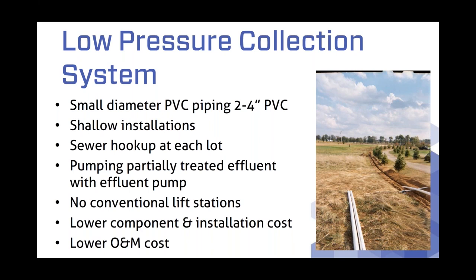There's a sewer hookup at each lot, just like a conventional municipal system. After the collection system is in, the contractor brings a sewer stub-out to each lot with a cap on it. When the home is being built, the septic tank and pump tank will be installed and connect to that sewer hookup. We're pumping partially treated effluent with an effluent pump — because of the low solids content, we don't have solids buildup, and we maintain an adequate scouring velocity. We pump directly to the advanced treatment system. Clean-outs are installed along the way for maintenance.